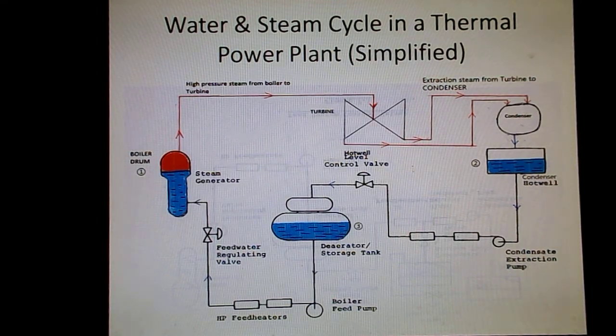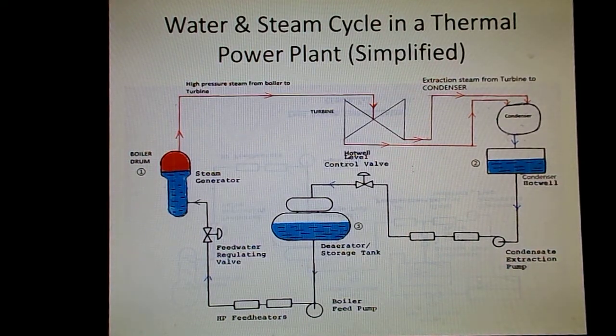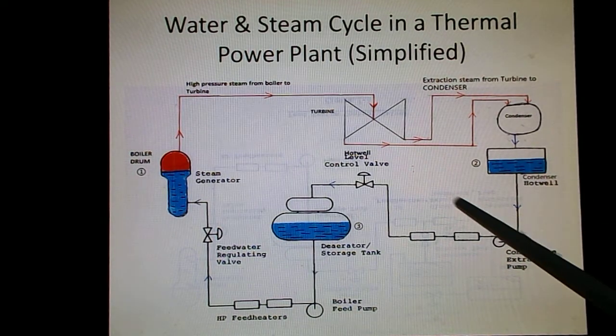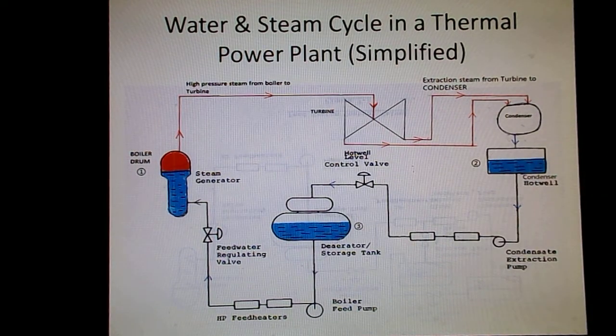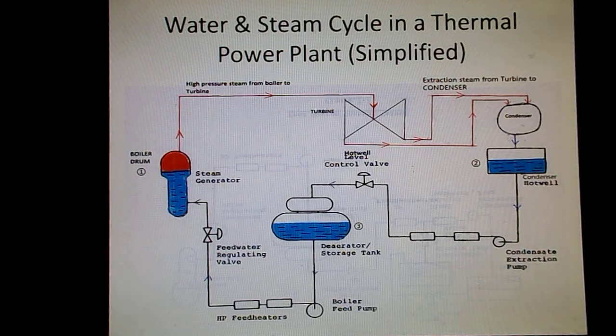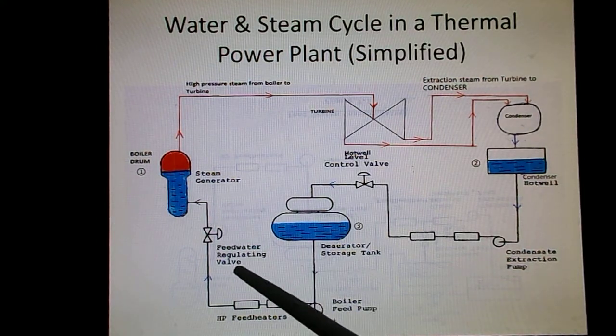We require only two control valves and two controllers to maintain the level in all three tanks. To maintain the condenser hot well, we have the hot well level control valve. To maintain the boiler drum water level, we have the feed water regulating valve.